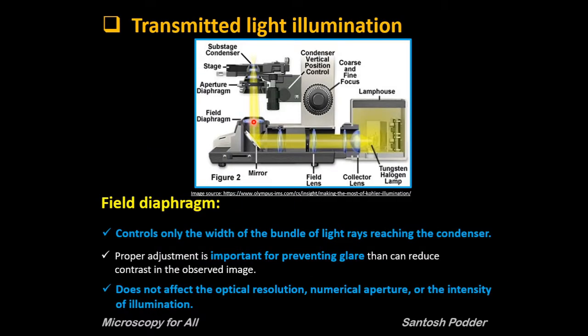The field diaphragm at the base of the microscope controls only the width of the bundle of light rays reaching the condenser. Proper adjustment is important for preventing glare that can reduce contrast in the observed image. If you open the field diaphragm too far, scattered light originating from the specimen will degrade image quality. The elimination of excess light is very important, particularly for samples with inherently low contrast.